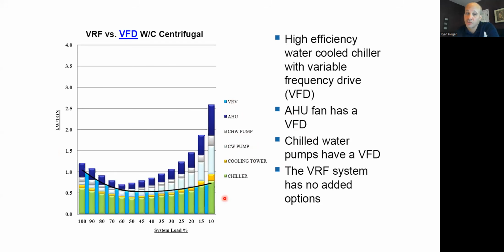Once again, it's not always true because I can get chillers that are way down here for energy, which chops the whole thing off. And I could do a better job on fan energy. Instead of putting a regular air handler in, I could do a VAV air handler. I can cut this fan energy in half. And I can get more efficient pumping systems and put VFDs on the pumps. I can do better than this. Like, obviously, the person that made this chart was a VRF fan. They picked the worst chiller plant they could find, right, and the worst air handlers, and compared it to a regular VRF system. I could get a really good chilled water system and get the total stacked line to be below this. But many systems are not. They're above this on VRF.